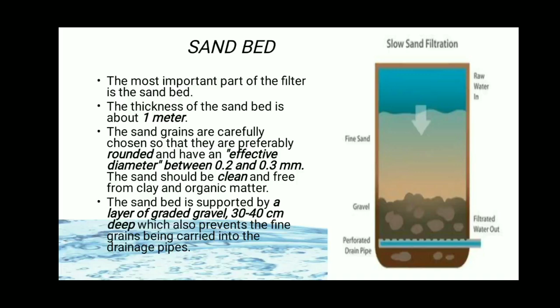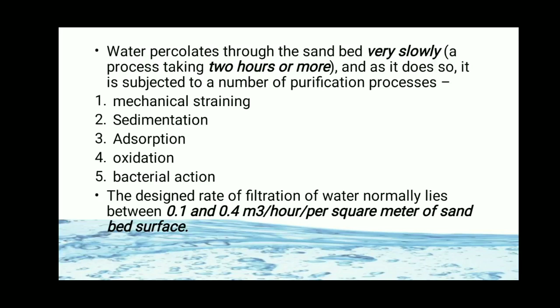In the sand bed, the water percolates very slowly. It may take 2 hours or more for passing. So a number of purification processes occur, like mechanical straining, sedimentation, adsorption, oxidation and bacterial action. So filtration rate is 0.1 to 0.4 m³ per hour per square meter of sand bed surface.